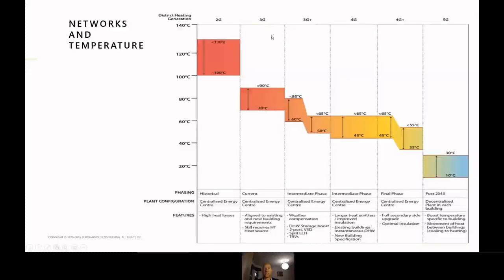As we go through generations, currently the industry standard has been 3rd generation, which are supply temperatures of below 90 degrees with return temperatures around 70 degrees. We then started looking at 3rd generation plus, which have higher temperatures but allow some flexibility using weather compensation in the summer to reduce temperatures, but are still relatively high. And then we're looking at 4th generation, which is where a lot of the industry is moving towards, with lower temperatures below 65, hopefully below 60.